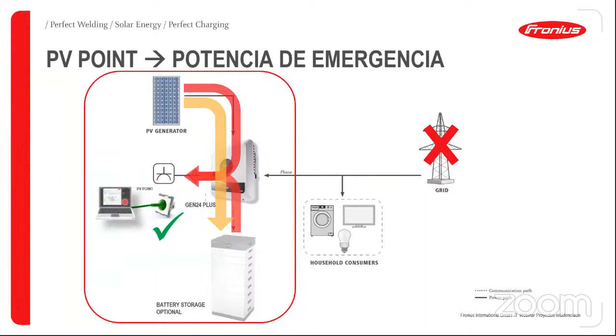So we can configure this inverter in two different voltage ranges, 110 volts or 220 volts. I know some consumption in the residential area is at 110 volts, but some of it is at 220 volts, so it depends on the country. We can also set up the conditions of the inverter. If, for example, we set 110 volts in the output, we can use 1.8 kilowatts in this PV point.